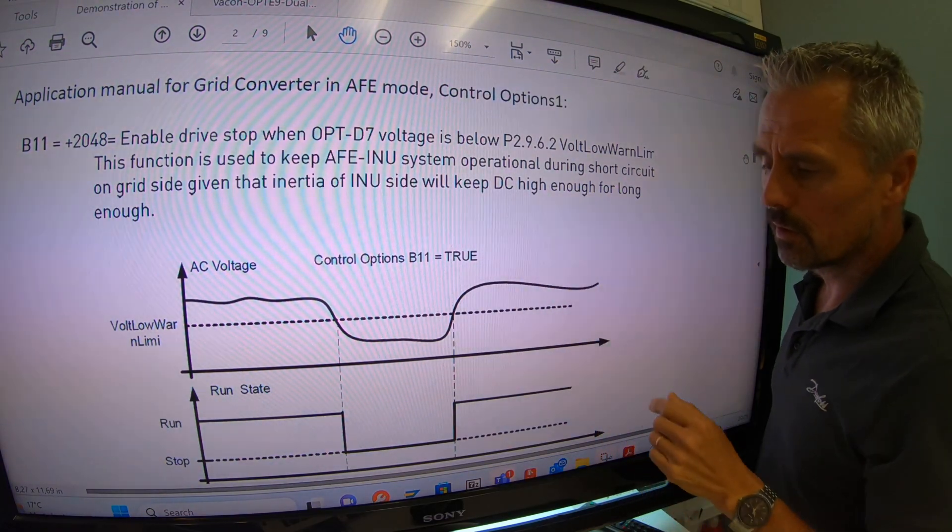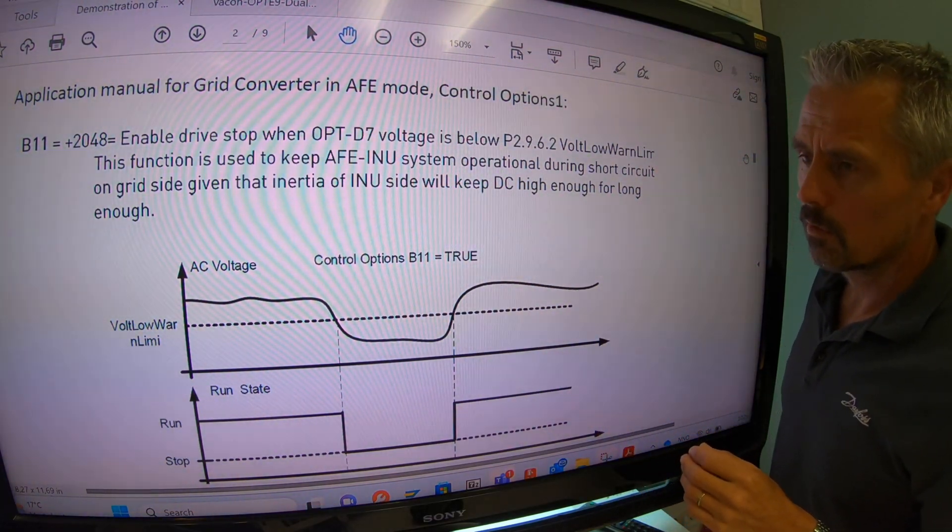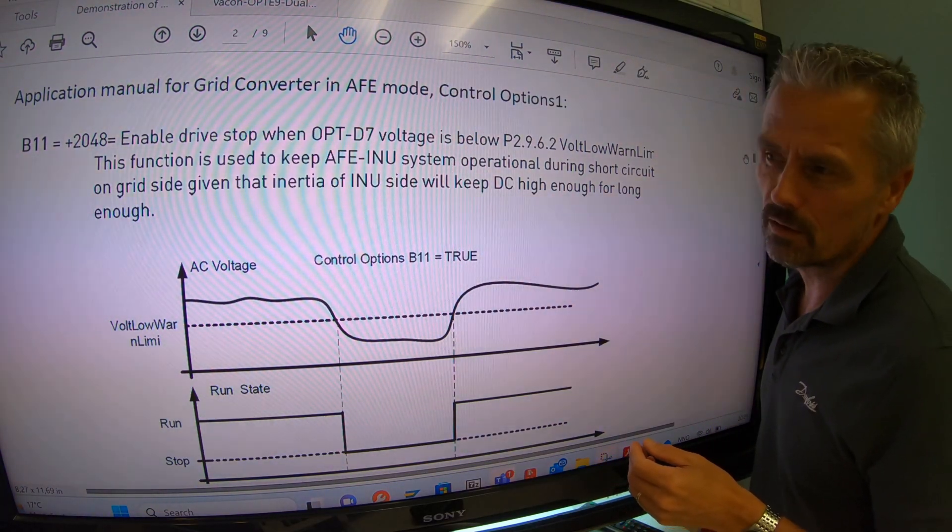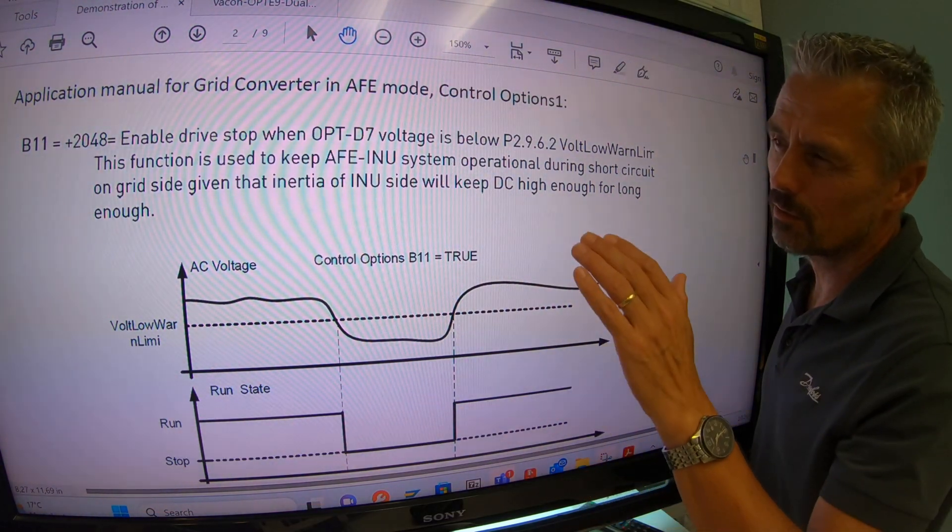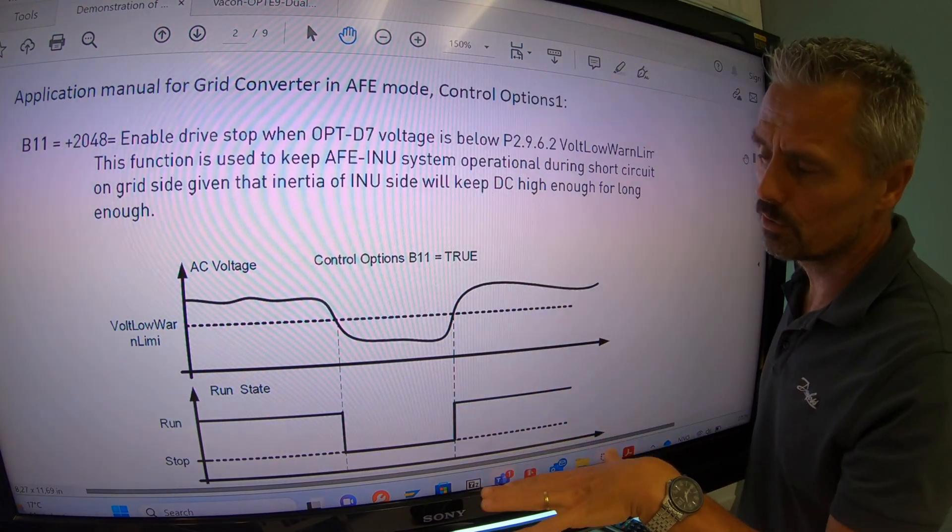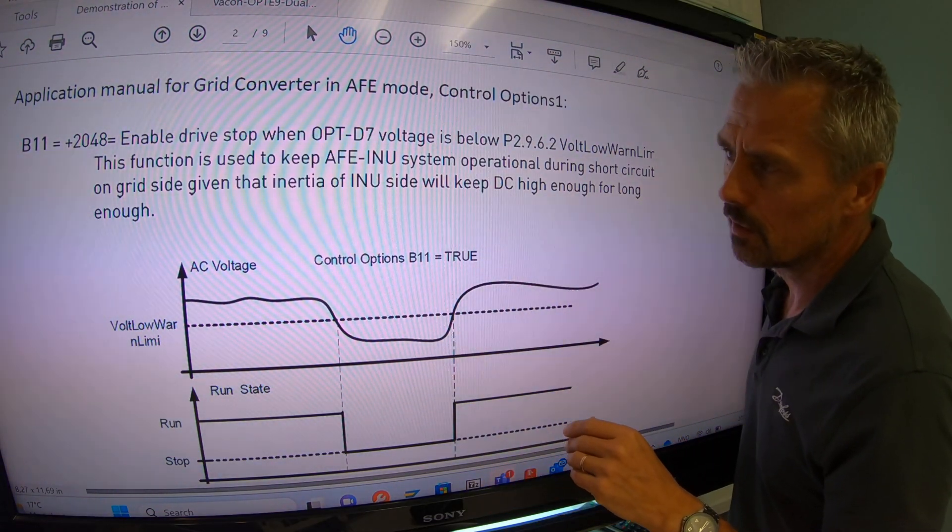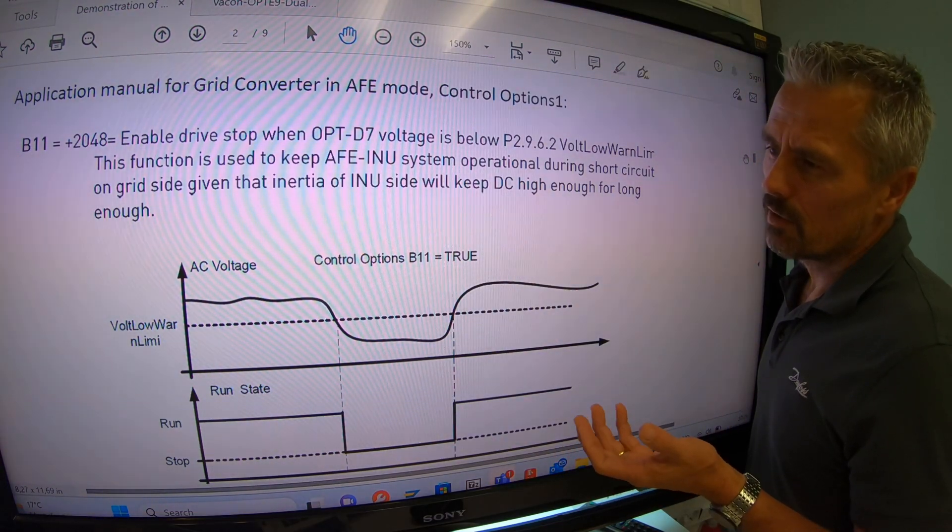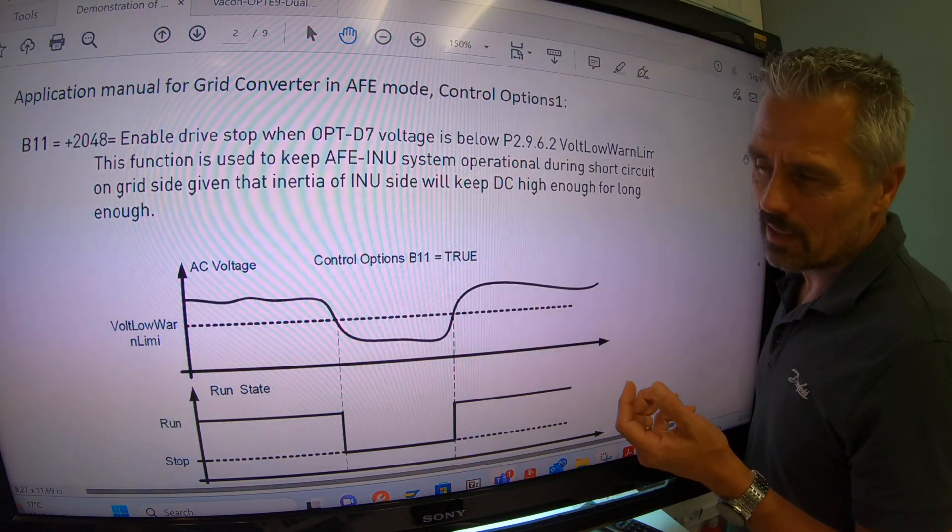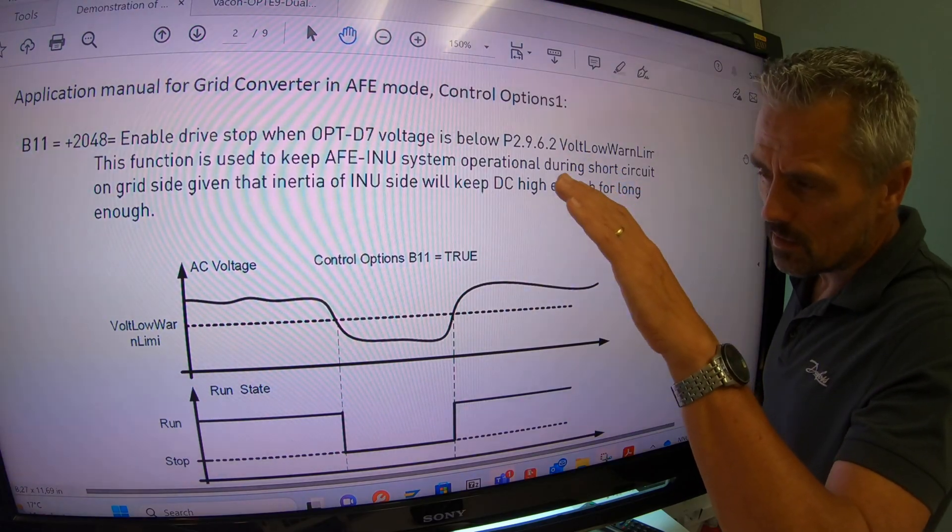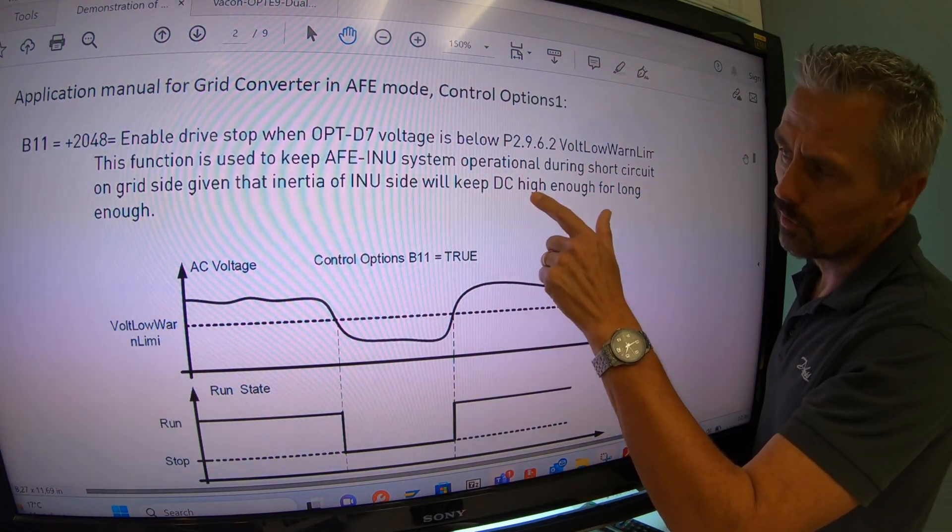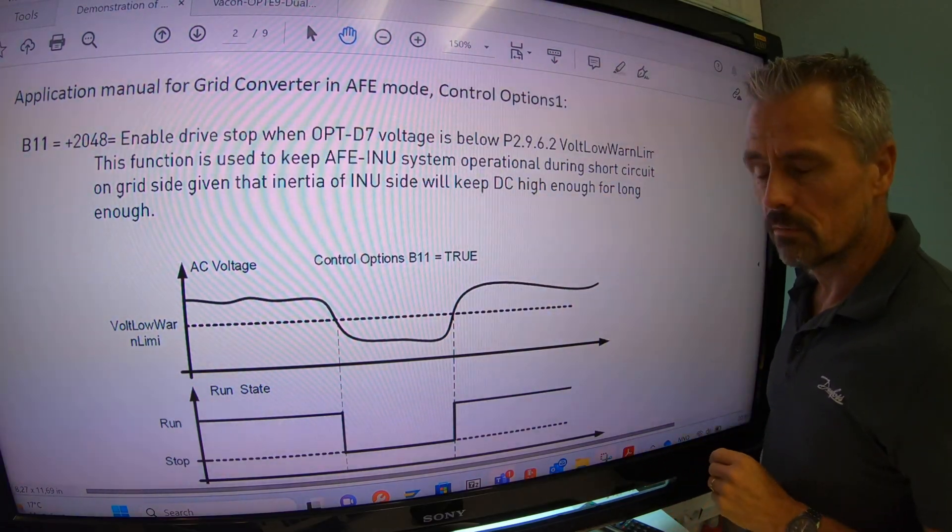It needs to be above the under-voltage trip level. For a 500 volt drive, which usually have a nominal of 675 volt, that means that you can go from 675 down to 480 something. And for a 690 volt AC drive, which have a DC voltage of about 1000 volt, then the DC voltage cannot go lower than about 600 volt. Because otherwise it will just game over.